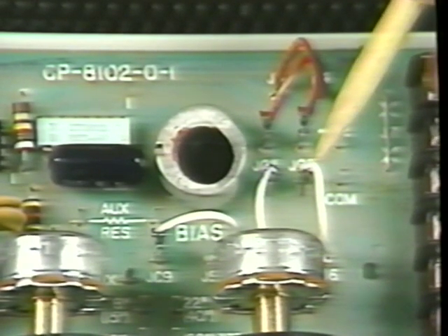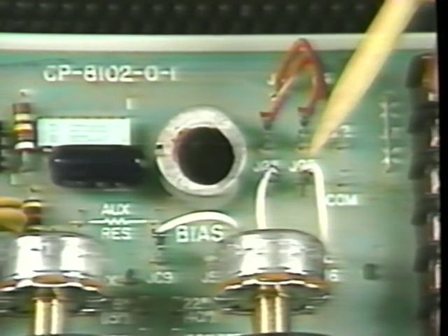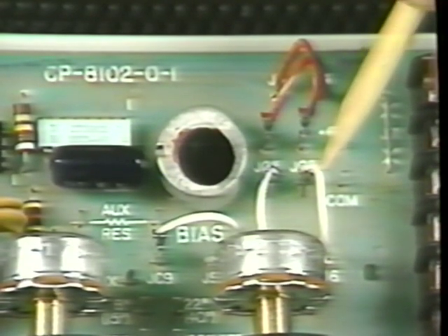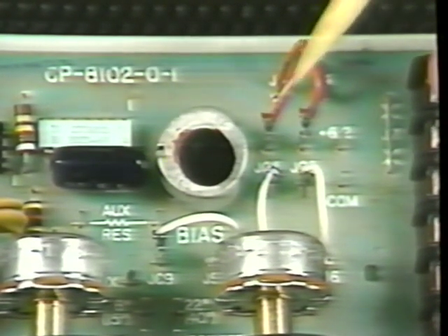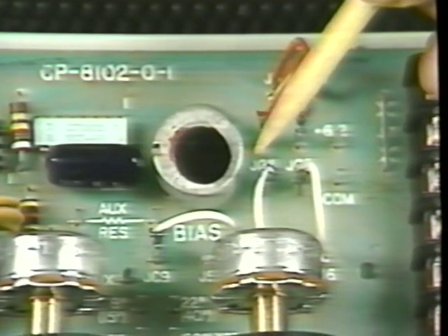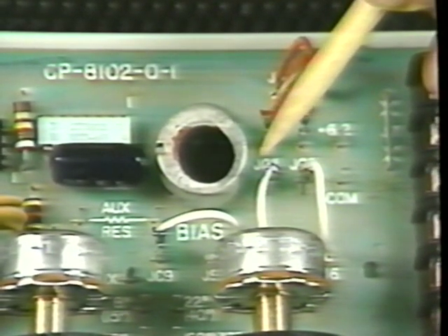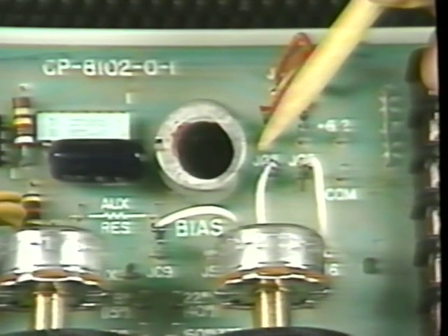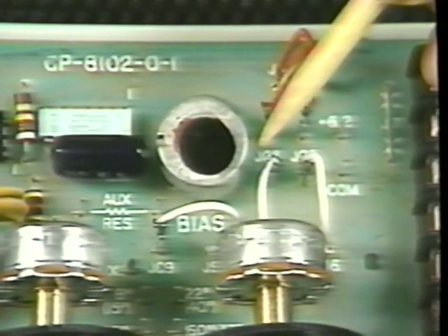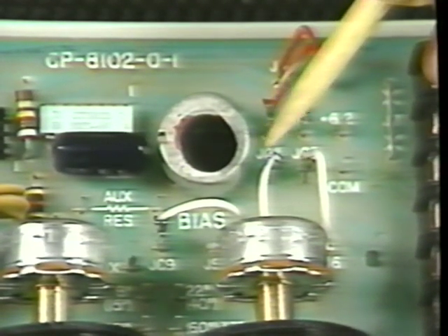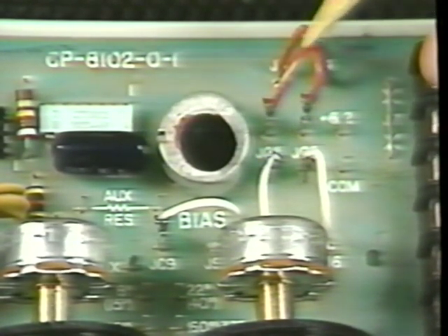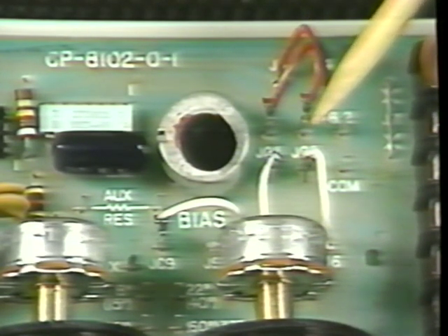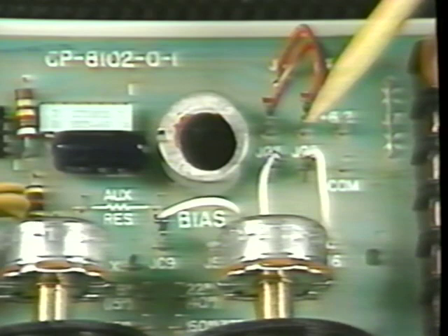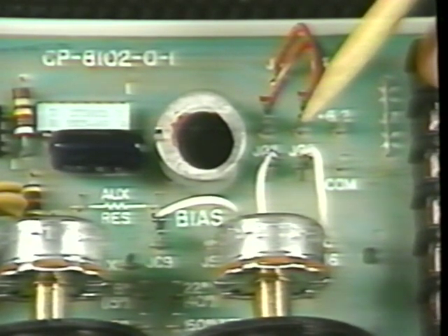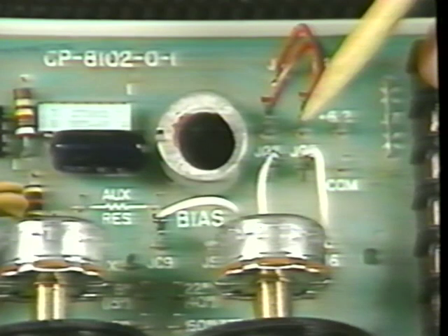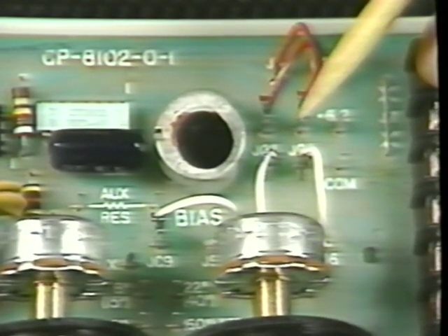A simple rule that determines the reset of this controller is as follows. When the positioning of the two jumper pairs is the same, the reset is reverse. An example of reverse reset is hot water reset, which we'll describe later. When the position of the two jumper pairs is different, as we see it here, then the reset of the controller is direct. For example, direct reset of cooling based on outside air.